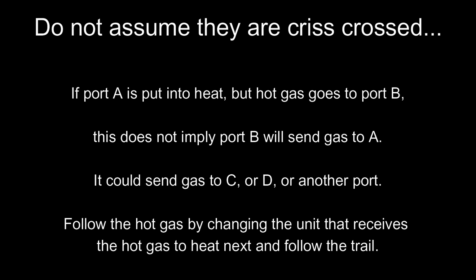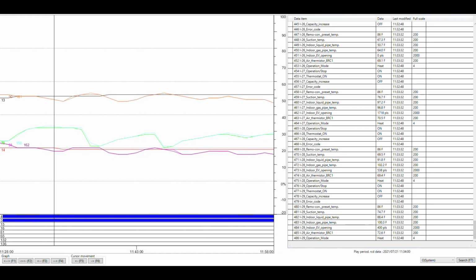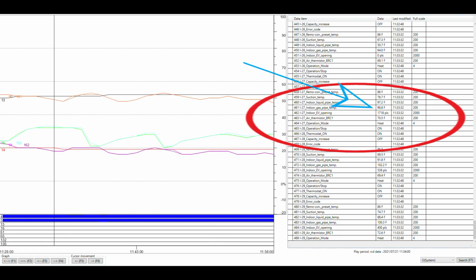We changed port B to heat. The hot gas went to the next group address in line, so we're going to switch that one over to heat now and see what happens. You can see switching the next set of ports over confirmed what we thought, and the hot gas went to I-27, which is group address 102 on our as-builts, which is port B of the branch box that this unit got wired to.